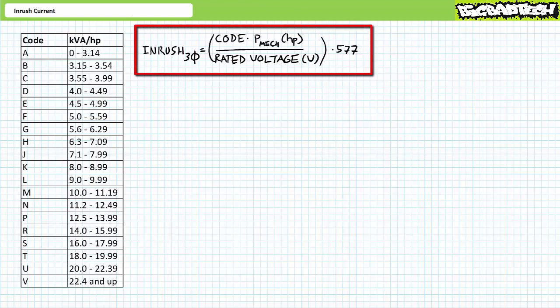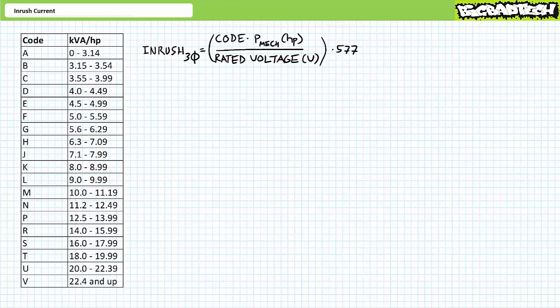The formula for a three-phase AC motor demonstrates that inrush equals the code number times the power in units of horsepower divided by the rated voltage times 0.577. Note the placement of the parentheses for those who wish to enter this formula into a calculator in one pass. As illustrated in the table, each letter has a lower and upper numerical bound. Depending upon the application, you may wish to perform the calculation twice — potentially three times — to determine the minimum, maximum, and average anticipated inrush.